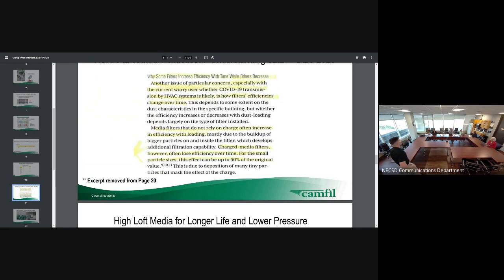So question, if we change the filter 3 times during the year, then 4 times a year. So if we switch filters, how many times a year do we have to change them? Once. So the asterisk to that is you do have some 1/2-inch filters throughout your district, a fairly small number. Those still need to be changed quarterly. Does the office want the small one? Exactly. Classroom 2-inch. 2-inch and 1-inch filters can be changed once a year. We recommend a change in August.